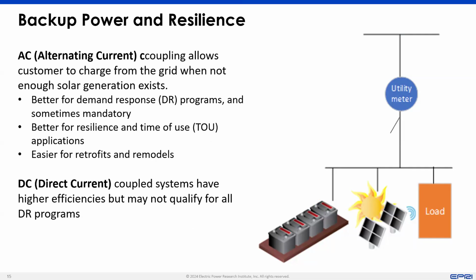The first is backup power or resilience that we've been talking about. Most new energy storage systems installed on homes are going to be installed with an AC interconnection. In other words, you can charge that battery from solar or from the grid. There are advantages and disadvantages to this. That AC connection is better for demand response programs. The fact that you can charge from the grid means you can charge when energy prices are low and discharge when they're high, and you're not reliant on solar charging your battery as you would be on a cloudy day if you're DC connected. You can't get that battery charged, and that hurts DR programs, for example.